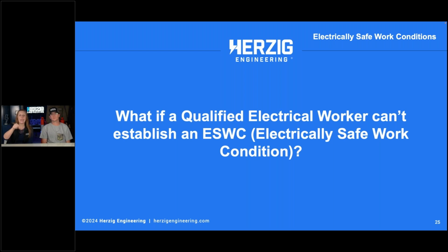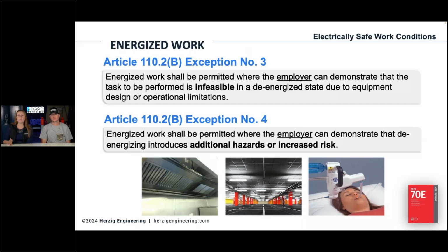What if a qualified worker can't establish an electrically safe work condition? Not won't, not doesn't want to - can't. There are really only two acceptable reasons: it's infeasible to do the work in a de-energized state, or it would cause additional hazards or increased risk by turning the equipment off. There are very few circumstances where either applies in today's world, but in case it's still a potential, there are exceptions.